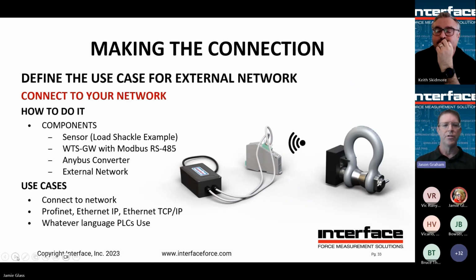Now, connecting to your network: we're looking at how to integrate from the actual sensor all the way through to the PLC and the network side. Here we have a wireless load shackle transmitting data wirelessly, which goes to a gateway, just like the prior picture. The gateway takes the digitized data and converts it to a signal, Modbus RS-485, which goes to an AnyBus module. From there we have a variety of options allowing conversion to Profinet, Ethernet IP, or Ethernet TCP/IP. It really depends on the environment you're working with and how to get there - it's essentially a language conversion.